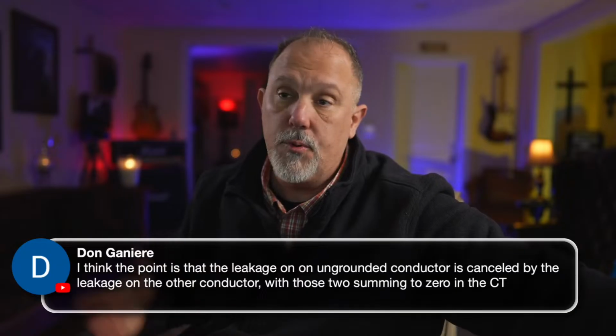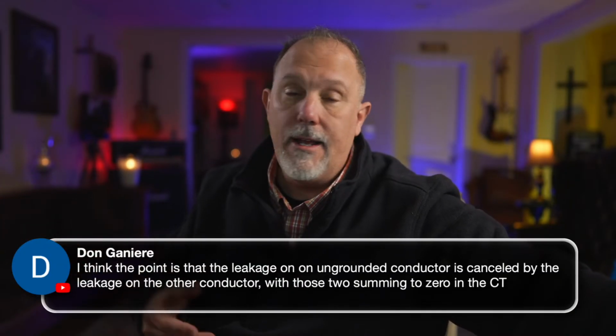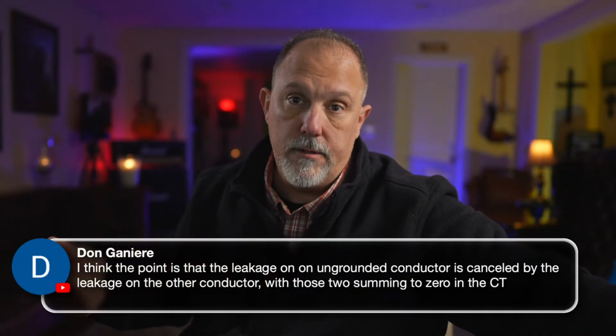And I would say, prove it. Put it in, go out and do the cancellation. Don't show me an equation, because here's the issue I have with equations. In the ballpark example, with over 1,000 feet of conductor, a very smart and good engineer did a lot of math and proved without a shadow of a doubt that it will trip on capacitive coupling leakage currents at distances greater than 250 feet, I think it was. And this was over 1,000. His opinion was, this will not work. It will always trip. They fixed the problems in the circuit. It is working today, in the rain, during every event. The handheld indicator trips the GFCI.